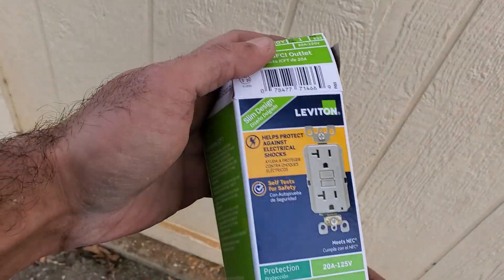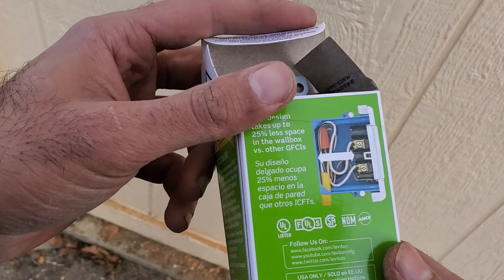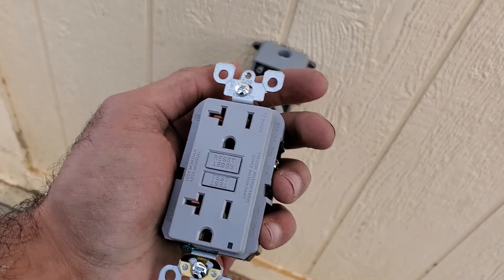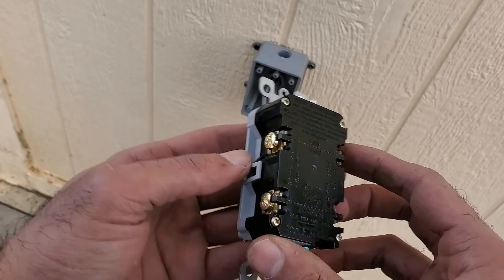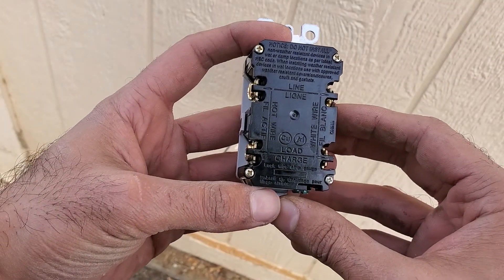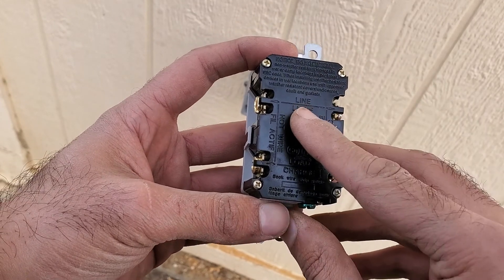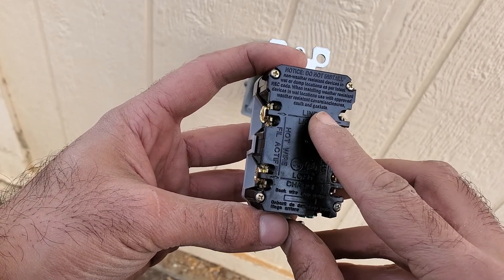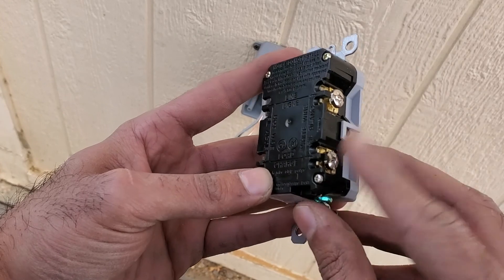Next it was time to wire up the GFCI. A GFCI is a safety device that breaks the circuit when a ground fault is detected. A ground fault is essentially any incident that causes electricity to be grounded instead of returning through the neutral wire. A GFCI senses this by monitoring the power coming in through the hot wire and the current going out through the neutral wire. When a difference of five milliamps of current is detected, the GFCI is triggered and the circuit is broken.